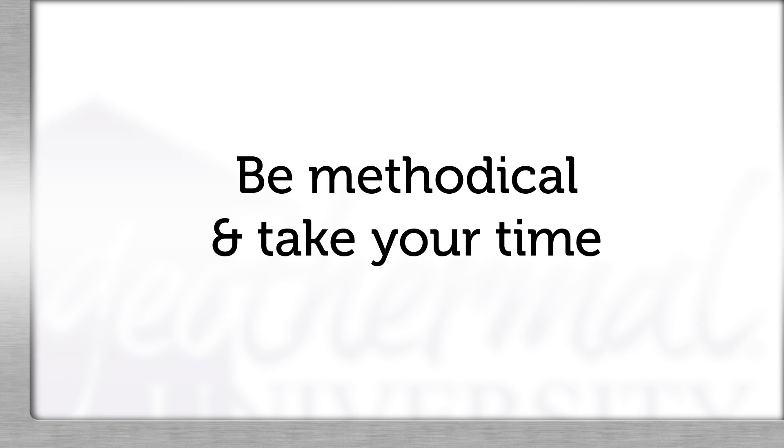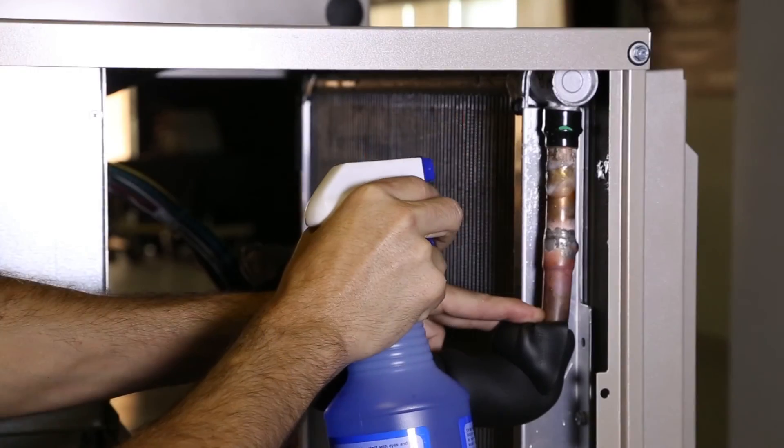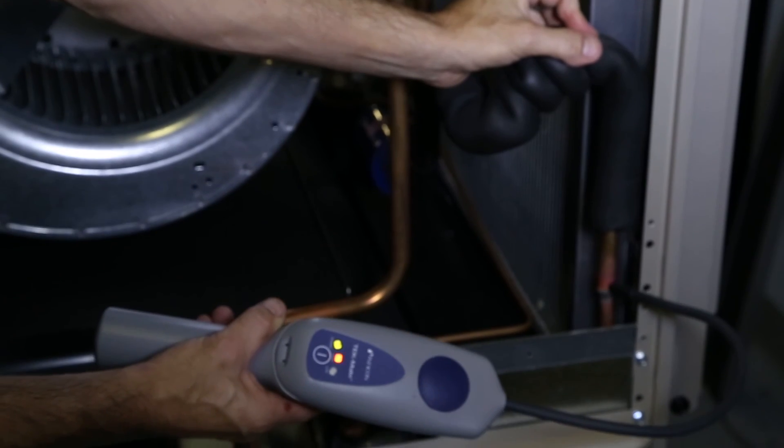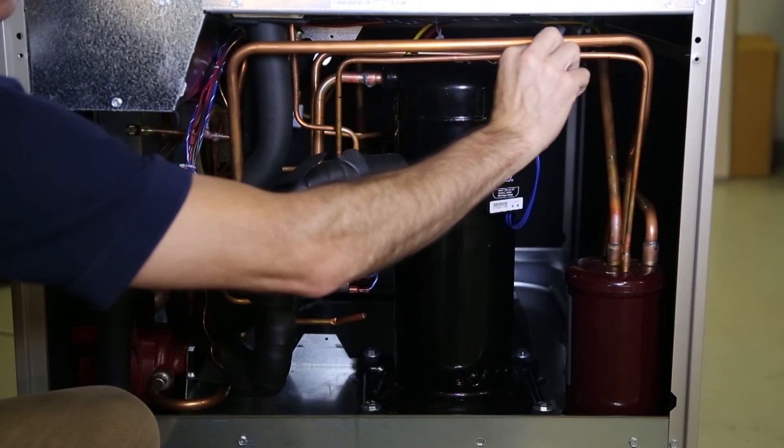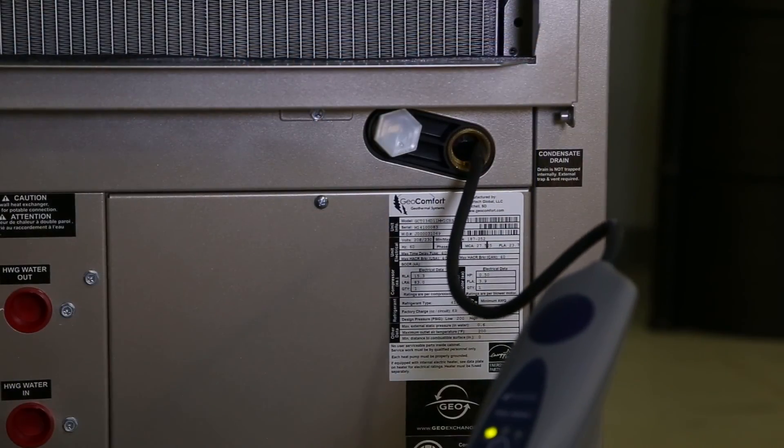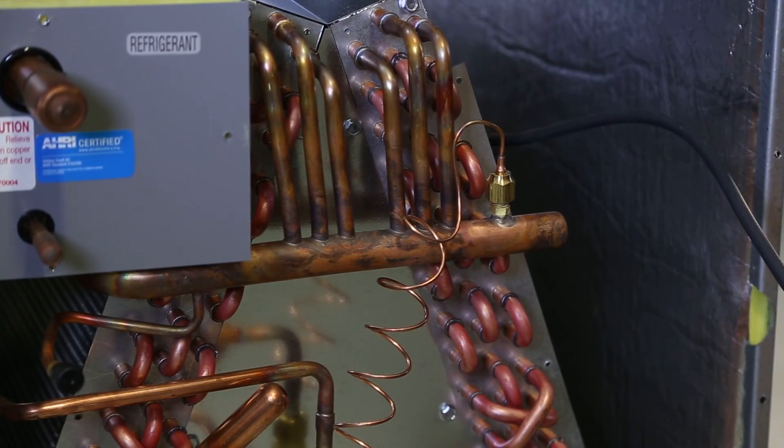In summary, please don't forget the following important steps when leak checking. Be methodical and take your time. Multiple leak detection devices may be necessary. Check the whole system including fusible plugs, braze joints, pressure switches, process tubes, service valve stems, Schrader valves, mechanical fittings, and bi-metal transitions or the aluminum to copper connections.